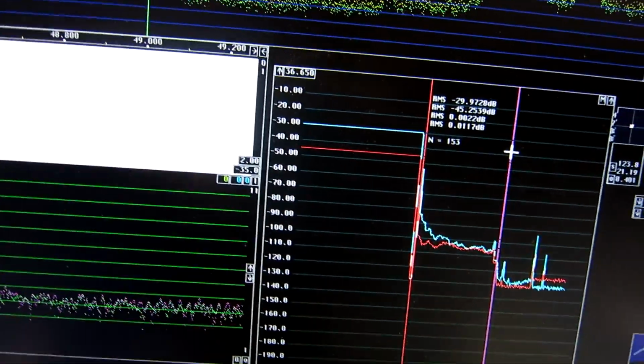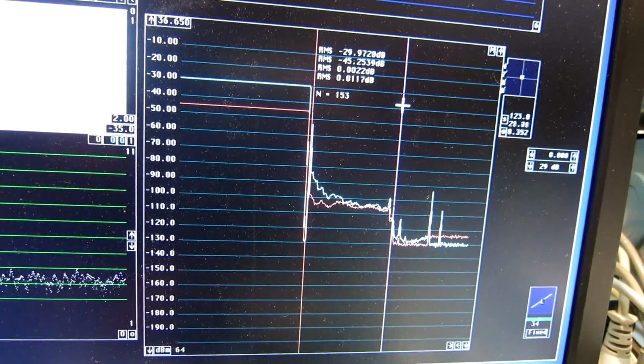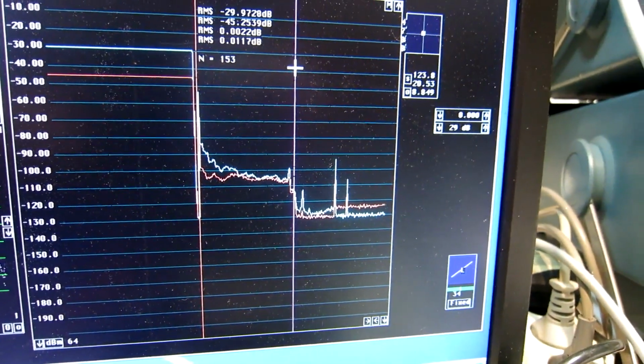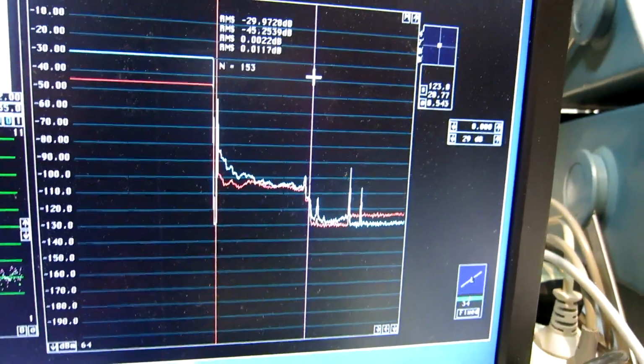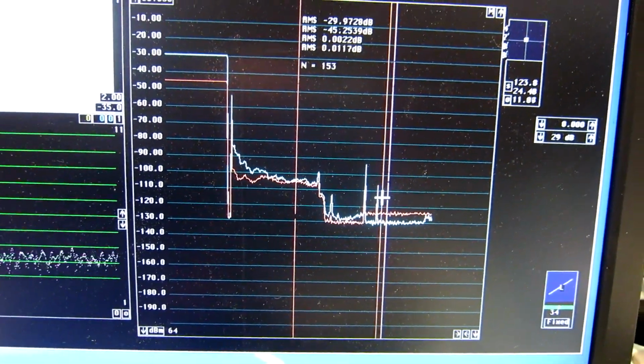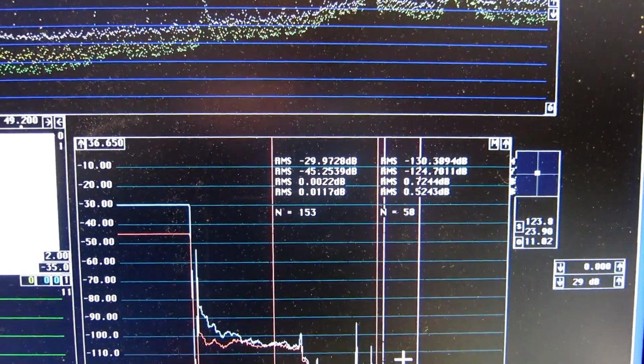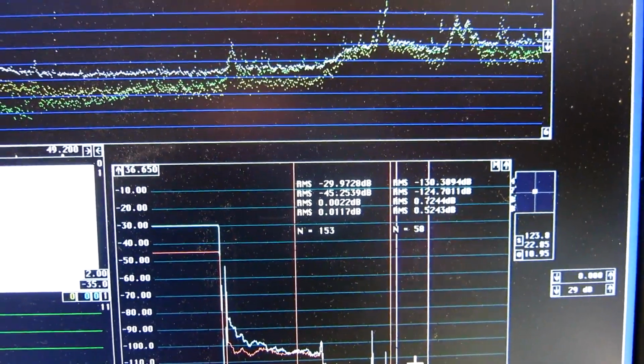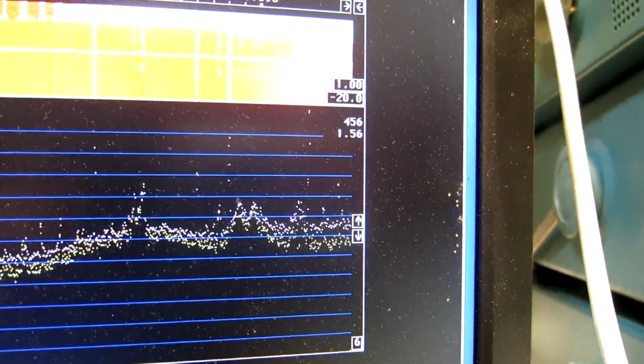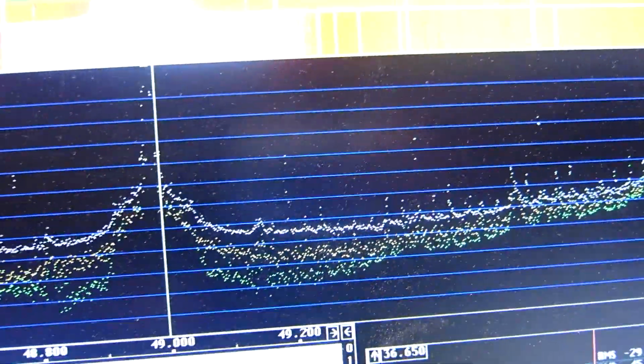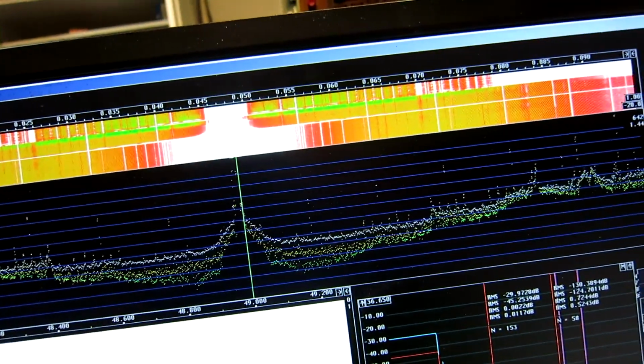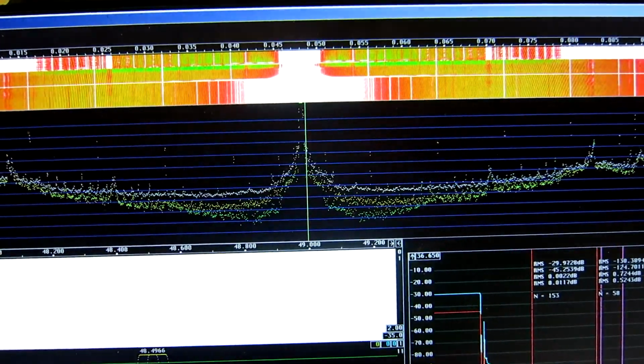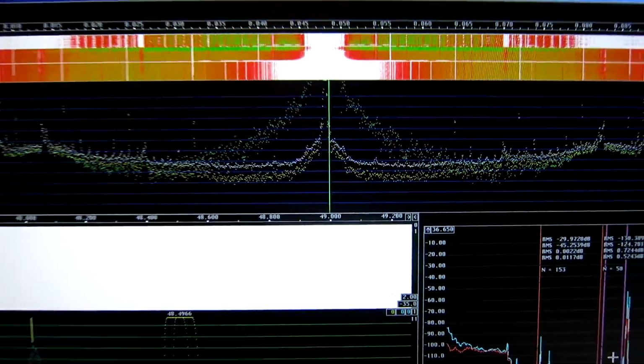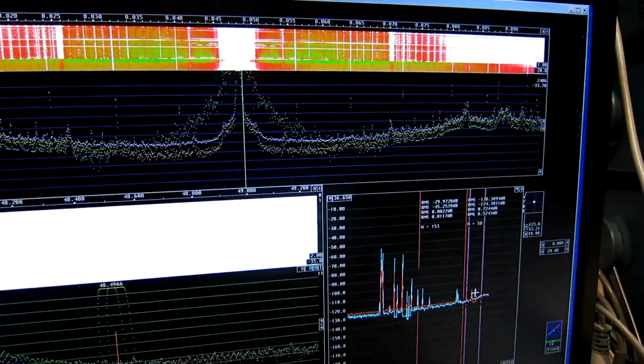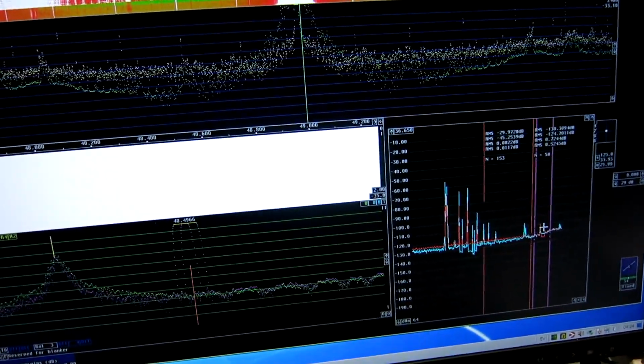I press Alt-Z. And the noise I see here is minus 130.4, and the correlation is about 2 dB below. So most of the noise I see here comes from that receive system. And now I see something is going wrong. I have to look for that. Stop this. Well, I had induced some grounding problem. I have to connect to ground here.